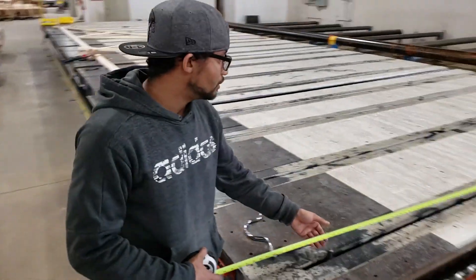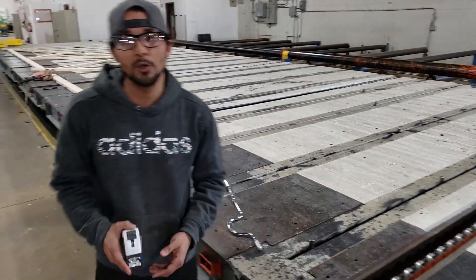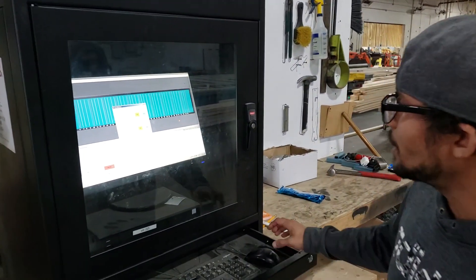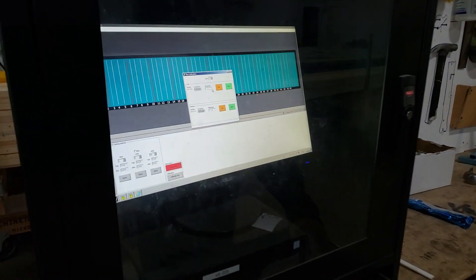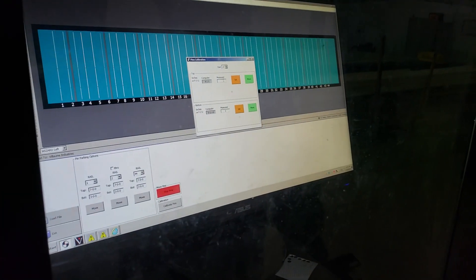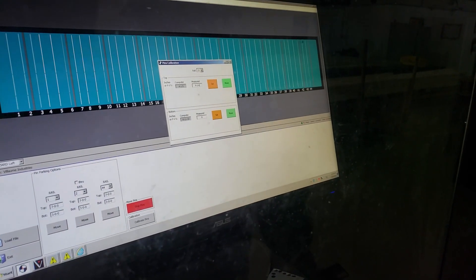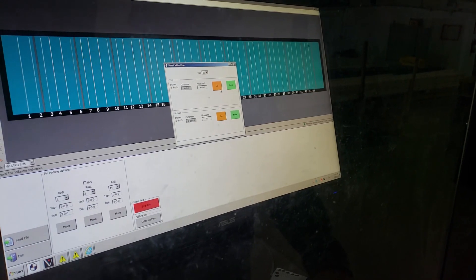So if you get one that's off like this, you want to go back to the computer. We measured 416 on the table, but it says 415 on the computer. So when you measured, you type in here — 416 — then you hit Set.